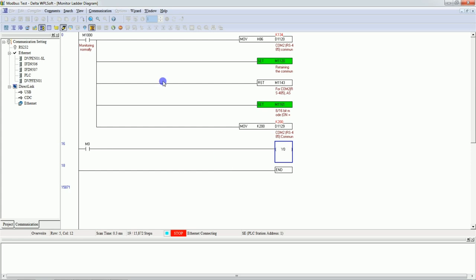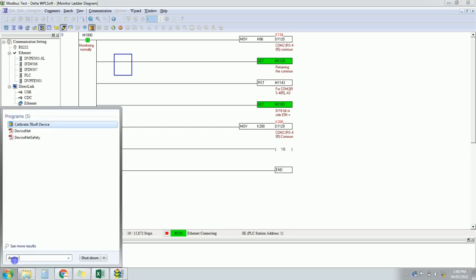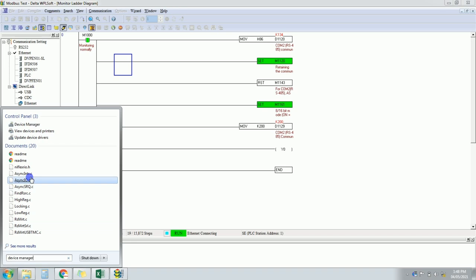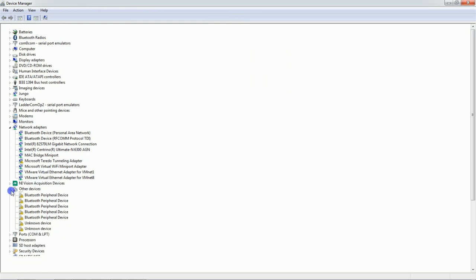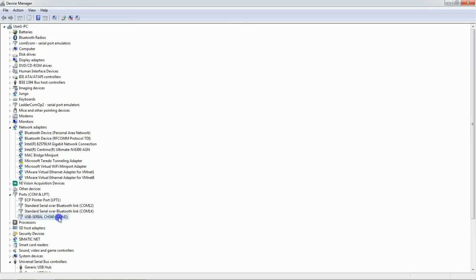We are downloading the program to the PLC — put it in Run mode. The PLC is connected to the laptop through USB port. For Modbus you need a USB to RS485 converter. I have connected a USB to RS485 connector and it is connected to the PLC. Now go to Device Manager — we will check the COM port. We have COM port 4 here. You will easily get this USB to RS485 module in the market.